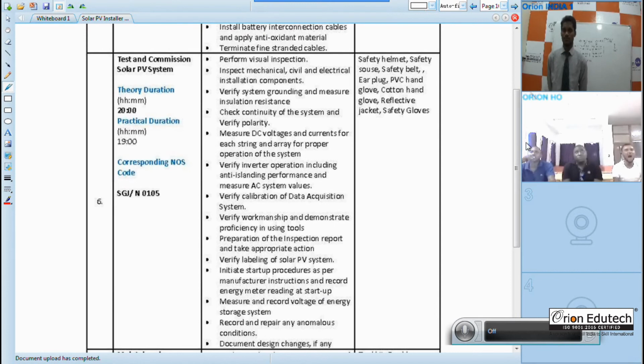If you come to the test and commissioning of a solar PV system, the key is to perform a visual inspection, inspect mechanical, civil and electrical installation components, verify system grounding and measure insulation resistance, check the continuity of the system and verify polarity, measure DC voltage and current for each connection and array for proper operation of the system, verify inverter operation including anti-islanding performance and measure AC system values, verify the calibration of the data acquisition system, verify workmanship and demonstration.